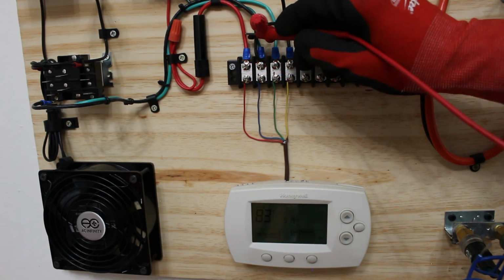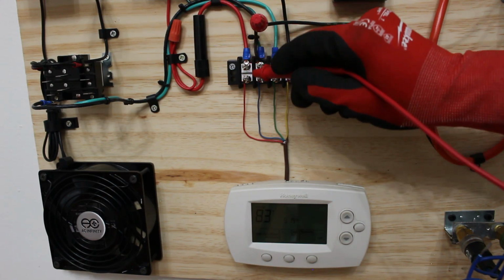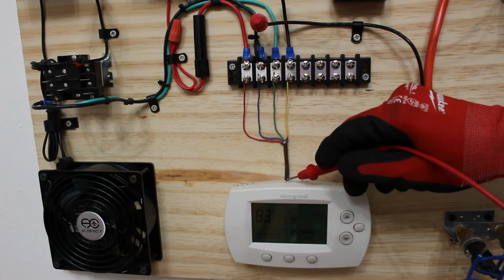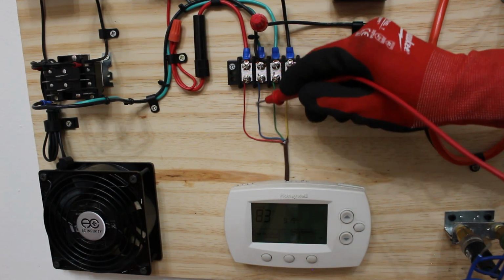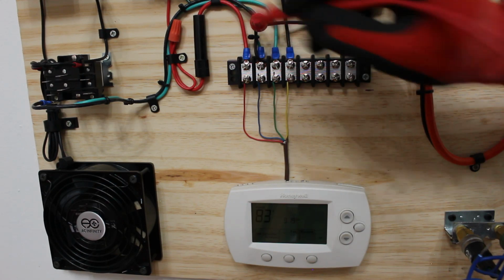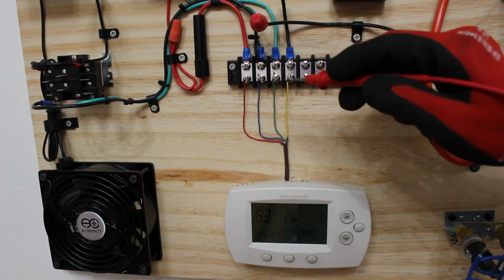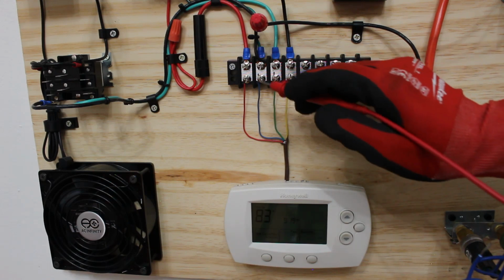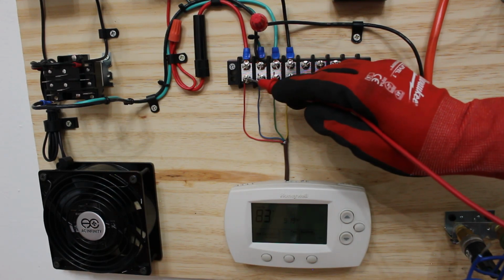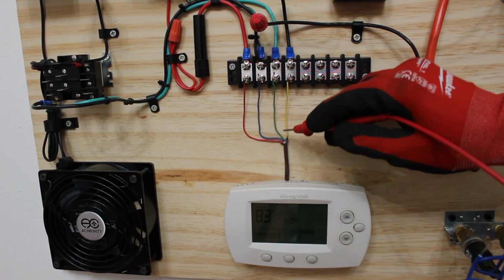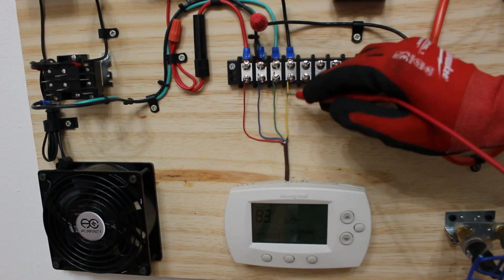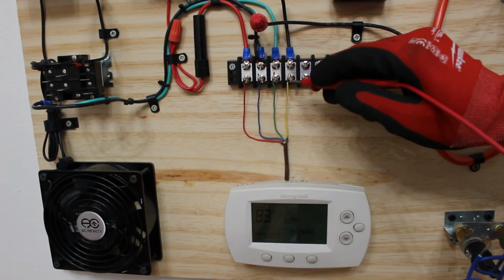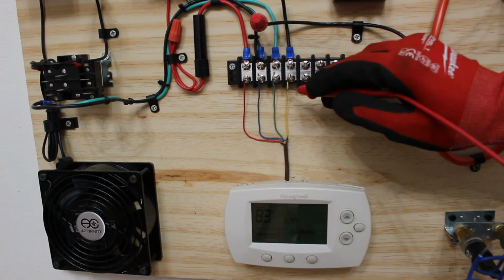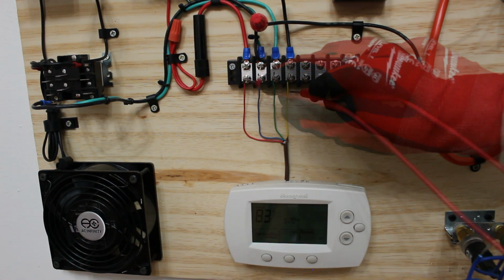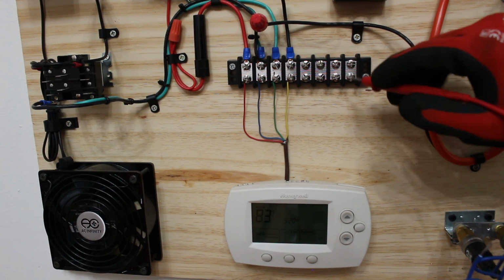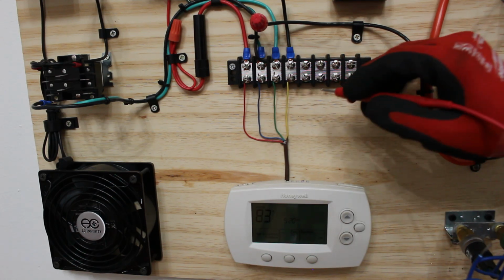This wire comes from our transformer. It's going to come in through R into our thermostat. It leaves through the blue wire back to common on the transformer. When you call for cooling, common stays where it is, but the red wire is going to close a pair of contacts and then send the 24 volts through this yellow wire. So this is going to be our starting point right here. Of course, this is our low voltage terminal block. We are dealing with 24 volts here.